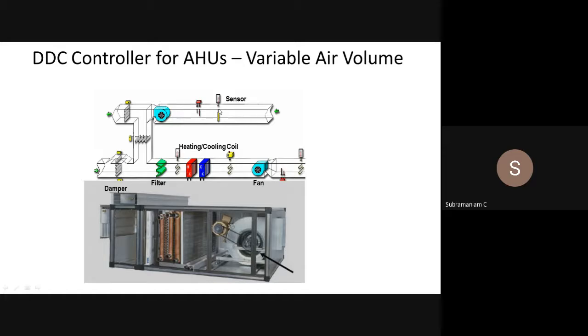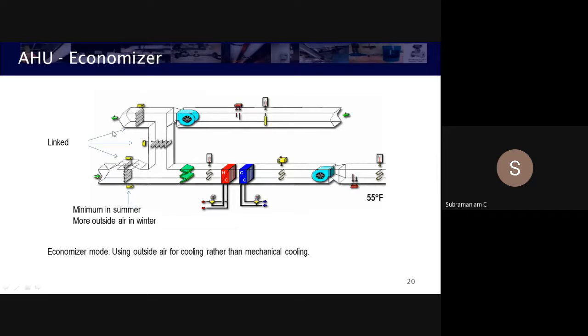You can put a sensor here. And we have to know from the HVAC designer exactly what the configuration of the air handling unit is. For example, this is an AHU economizer. The meaning of economizer is, if you see here, this is exhaust air, this is fresh air downside, and I am having a motorized damper here. I am having a motorized damper in the fresh air. I am having a motorized damper in the return air.